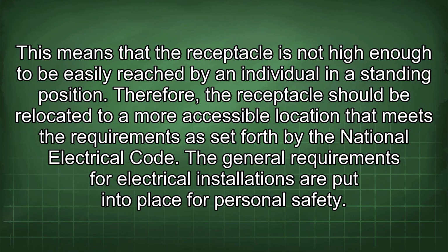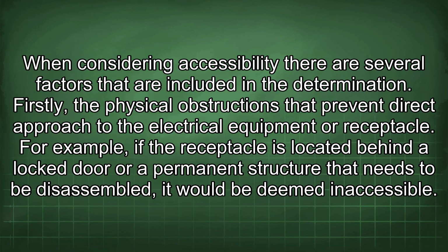National Electrical Code. The general requirements for electrical installations are put into place for personal safety. When considering accessibility, there are several factors that are included in the determination. Firstly, the physical obstructions that prevent direct approach to the electrical equipment or receptacle. For example, if the receptacle is located behind a locked door or a permanent structure that needs to be disassembled, it would be deemed inaccessible.